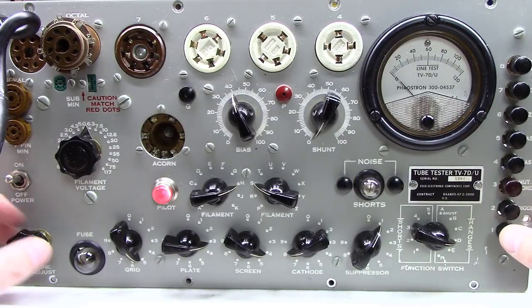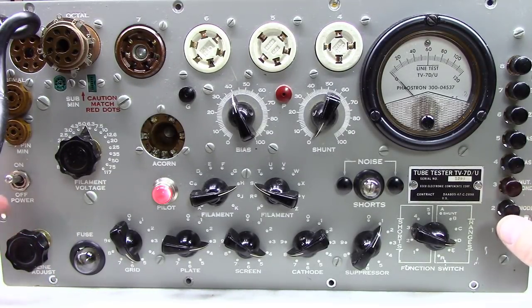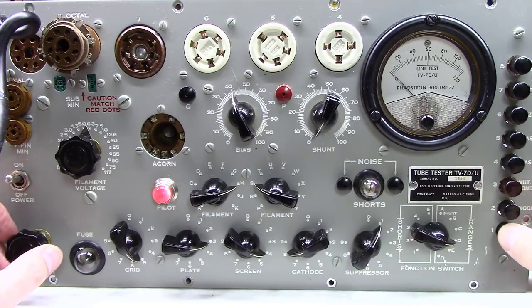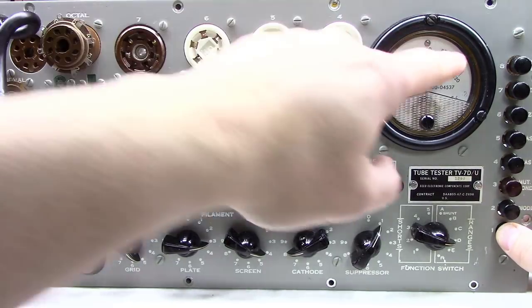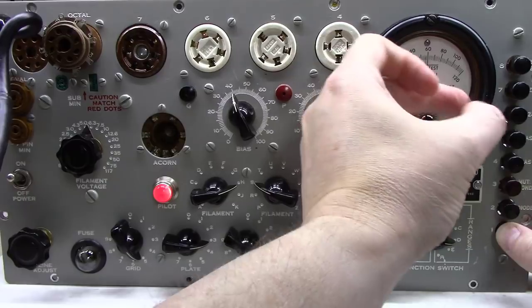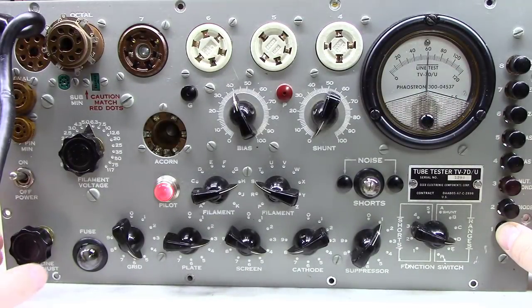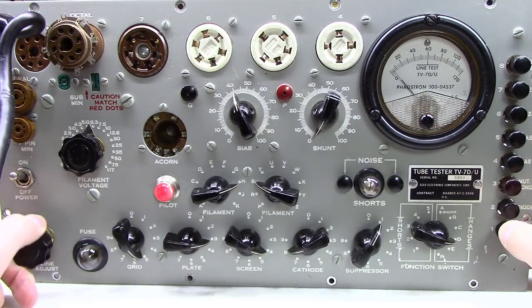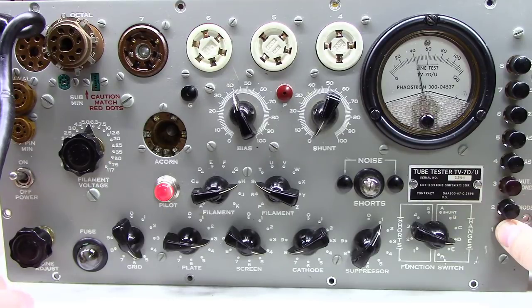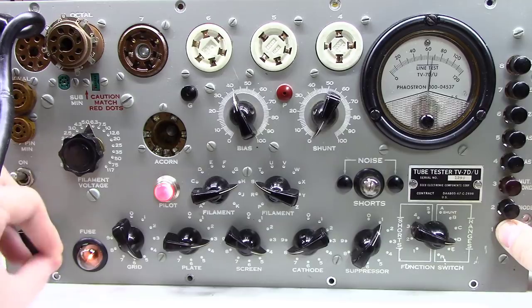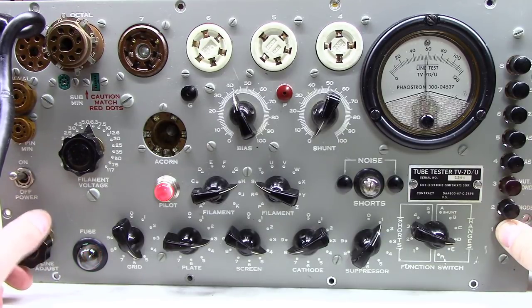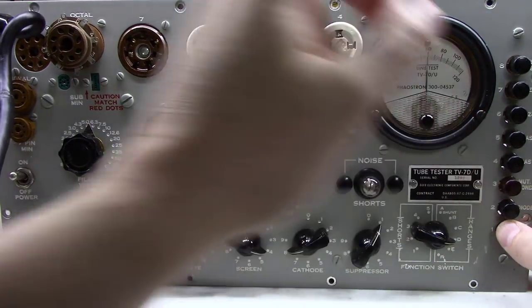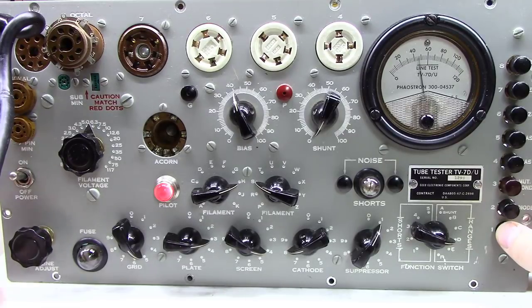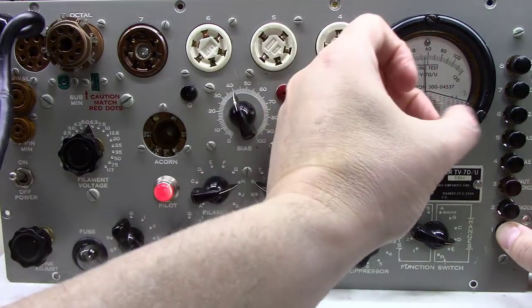One of the things we're supposed to do is hit this line adjust button here while turning the line adjust over here. And you're supposed to get that thing up on 60. Well, watch this meter. As I thump it, it goes up there. So if this thing was out of whack and it's sitting right here and you're trying to get it to go up to 60, you would turn it and get it along in here, but then you thump this meter and you bring it back and it's not on 60.